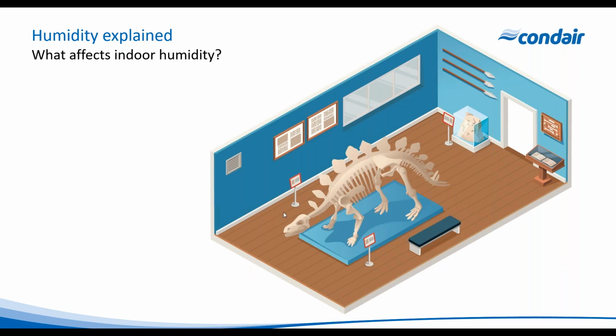So what affects indoor humidity in a room? Well, there are many aspects. The first thing would be ventilation. So doors and windows and mechanical ventilation is going to be something of a consideration. We're going to have an air change rate. And UK building regulations state that for every person in the space, you're going to require 10 litres per person per second. So we know we're going to be bringing that outdoor air into the occupied space.